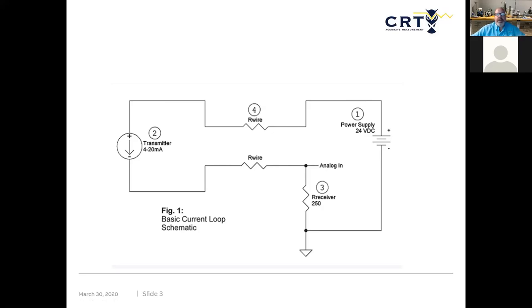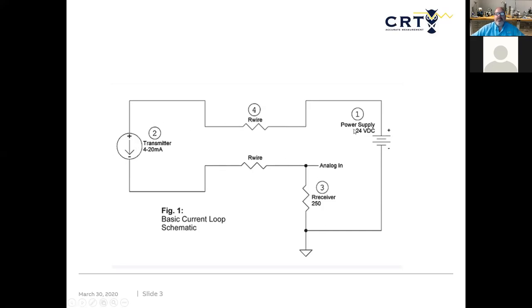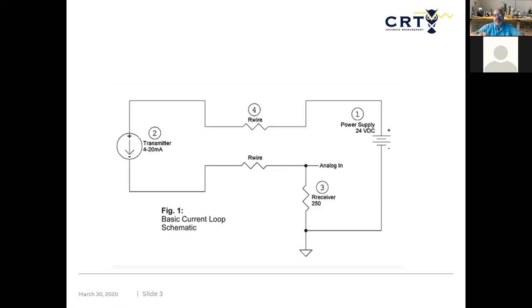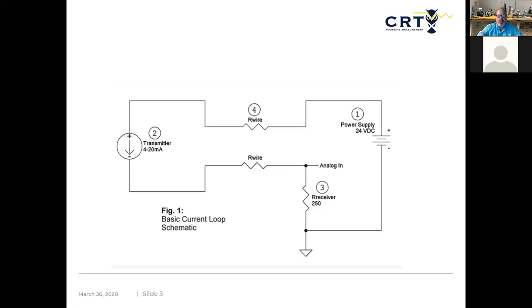I can't really measure the amount of milliamps by just putting two leads across that transmitter. I can measure the voltage, but I can't measure the milliamps. I have to be in series with the loop in order to measure that. You'll see that on most of the meters, you have a milliamp setting, and you have to put your probe into milliamp and then put it into series with that circuit.